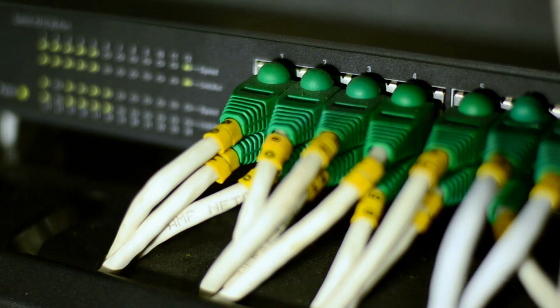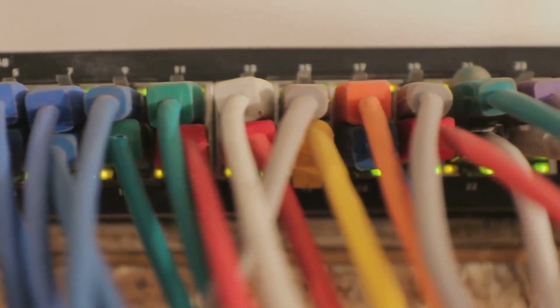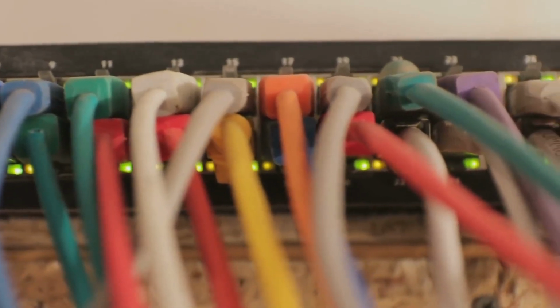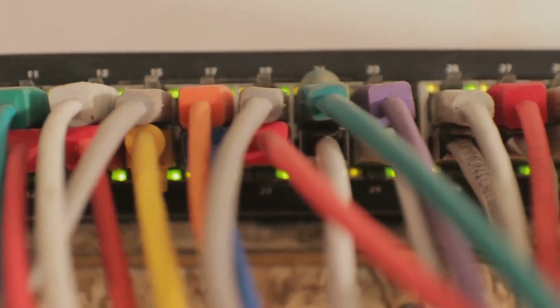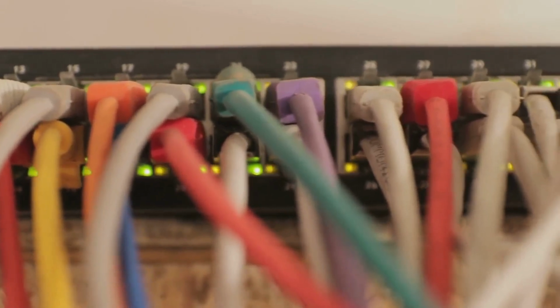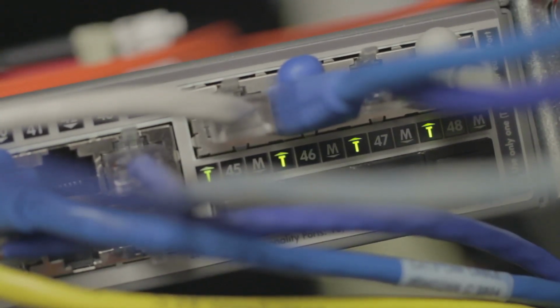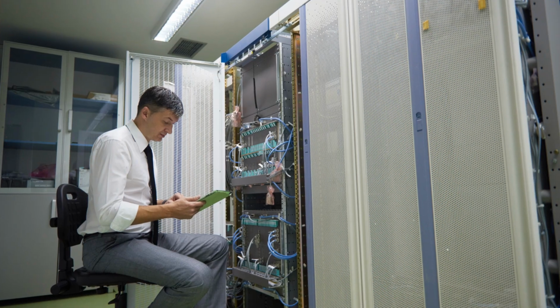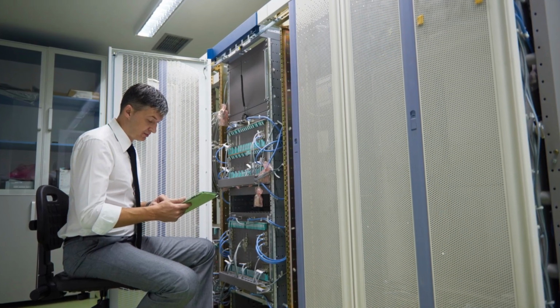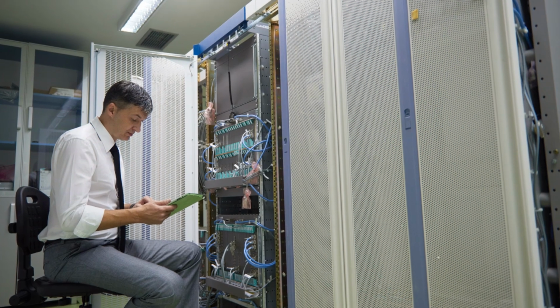To achieve true redundancy, the primary and secondary networks must be physically isolated. This means using separate switches, separate cabling, and potentially even separate power sources for the network equipment in each path. If both networks share a common point of failure, such as a single power supply for all switches, then the redundancy is compromised. The goal is to eliminate any single point of failure that could take down both networks simultaneously.